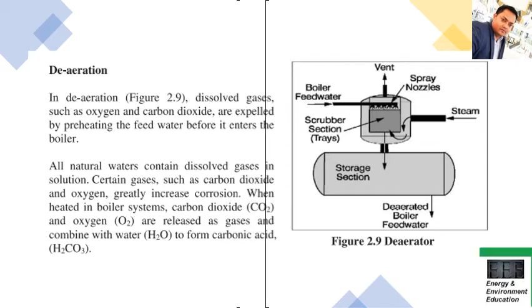Now, even the deaeration process has two parts, basically two processes, you can say, the mechanical and the chemical deaeration processes. I won't explain everything again about them, but just to give you a bit of insight into what's happening here. In the case of the mechanical deaeration process, you have two types, basically the vacuum type and the pressure type. In the vacuum type, vacuum pumps or steam ejectors are required to maintain the vacuum, and in that case you eliminate the oxygen content inside the water.